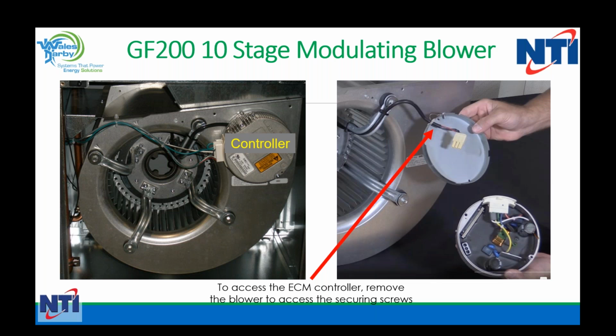Does it act as an ECM? Yes, a question just popped up on the screen. Yes, it does. It pulses. This is how we do our stages on that blower motor. It'll be based on timing and CFM and static pressure. So it's constantly going to try to fill a balloon, so to speak, as it ramps up through its 10 stages. The longer the heat demand is, the faster the blower will spin, because it thinks that because the heat demand is longer, the blower must need to run harder and move more air to support what's going on within the house. So that's what it's doing.